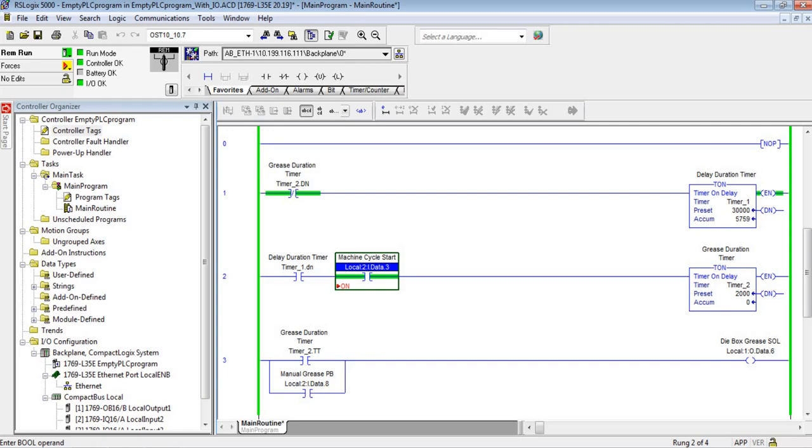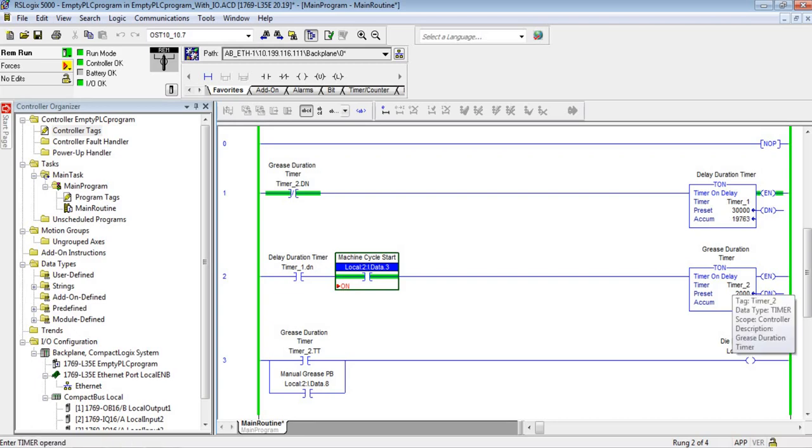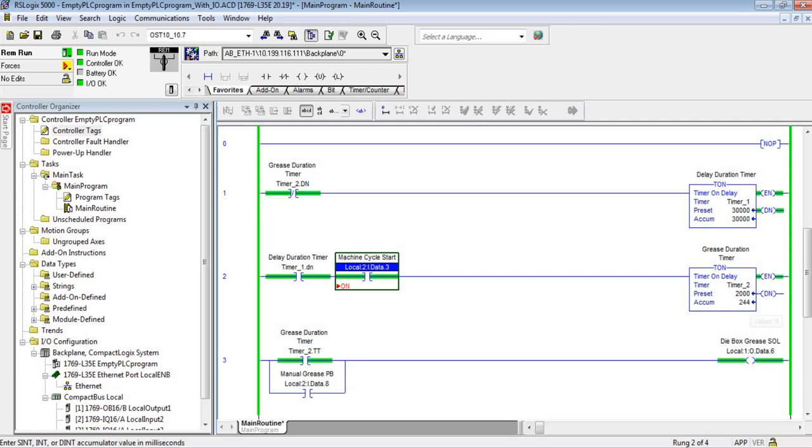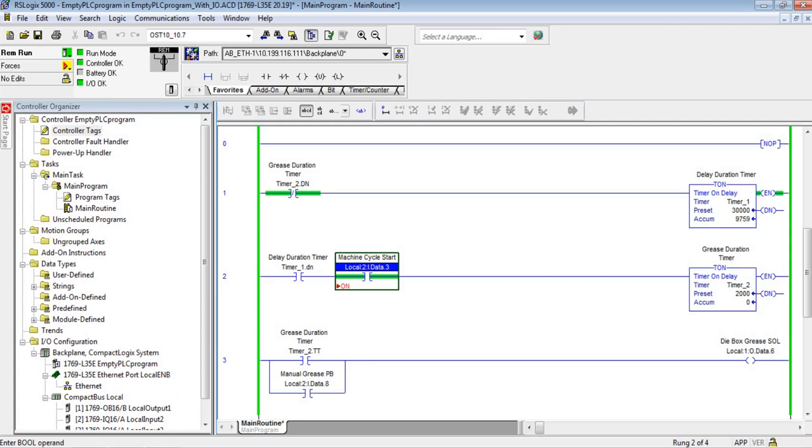The way this logic is structured is I need to run timer one for 30 seconds. When it's done - here's the done bit, the DN is the done bit - when I'm done and the machine is running, start timer two for two seconds. Timer two's timer timing bit, which is on while timer two is going between zero and two thousand, will turn on and allow the die box grease solenoid, which is an electric solenoid on an air pump sitting in a bucket of grease, to dispense the grease through the lines, through the manifold, into the die box.